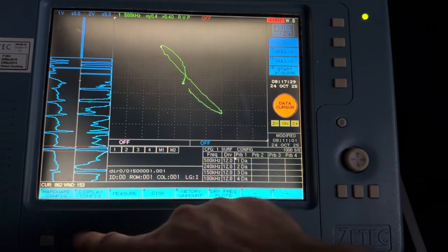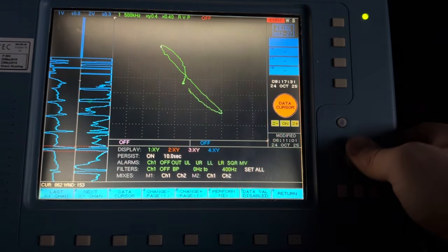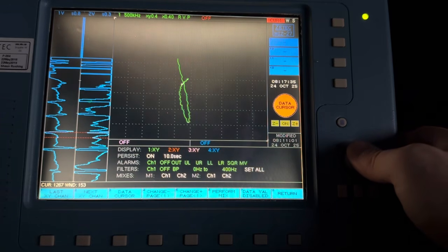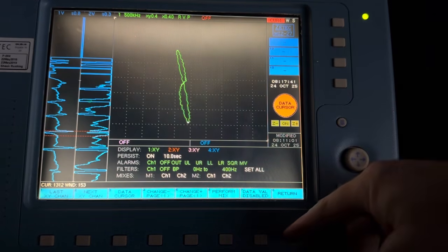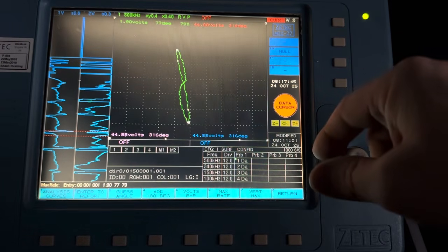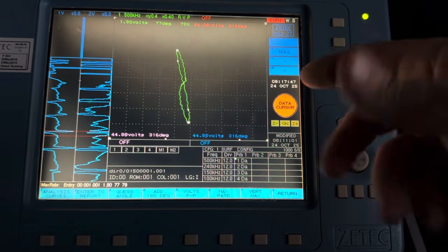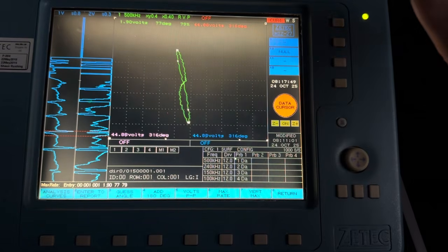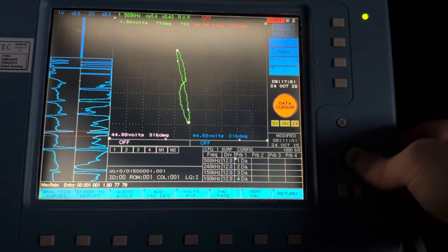Now, when I'm scanning in the proper direction, moving up the strip chart, the next indication is from an 80% flat bottom hole. Now it's going to be about, what, 80 degrees? That about right? 77 degrees, so that's also in the flaw plane. Anything from 0 degrees to 180 degrees is typically in the flaw plane.